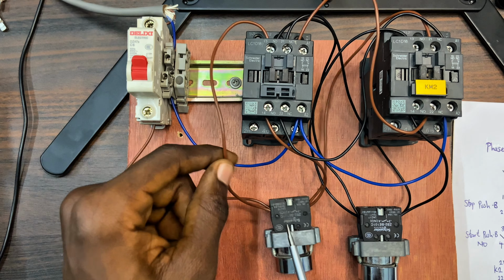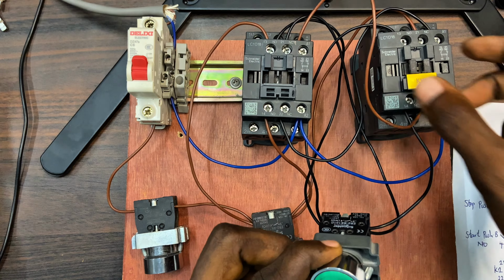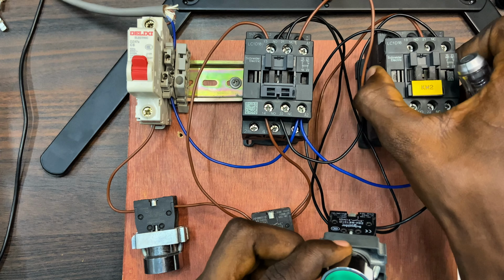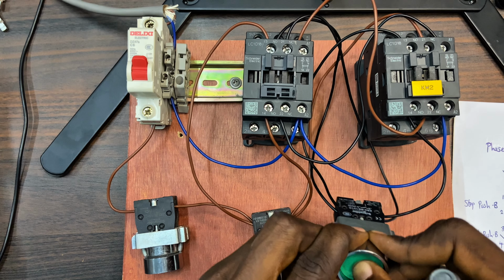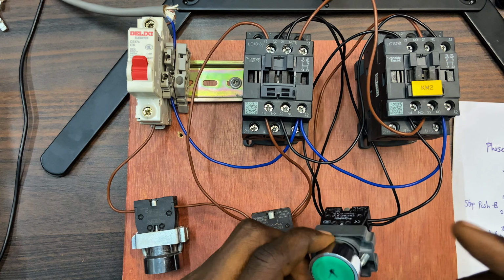Now, let me push the reverse push button and see what happens. You could see that the reverse contactor is not energizing. It is because of the interlocking. The interlocking is preventing simultaneous operation of these two contactors. We don't want these two contactors to be working at the same time. Hence, interlock is needed.